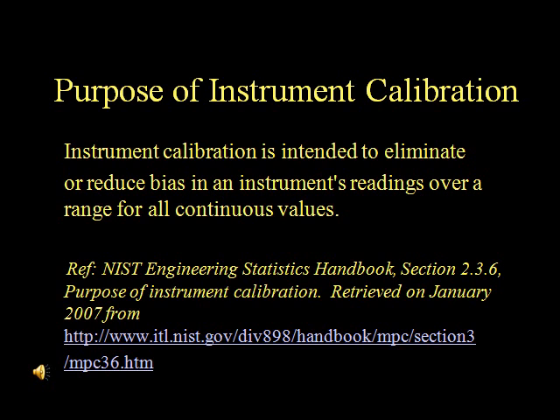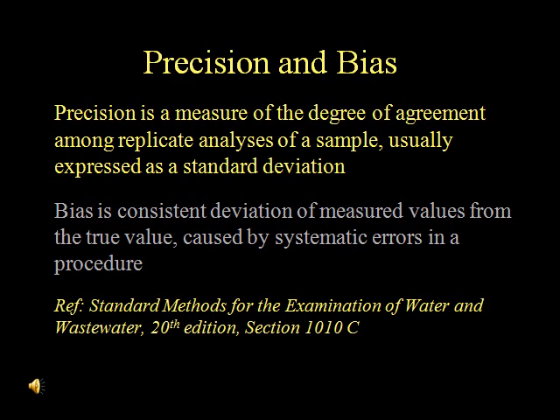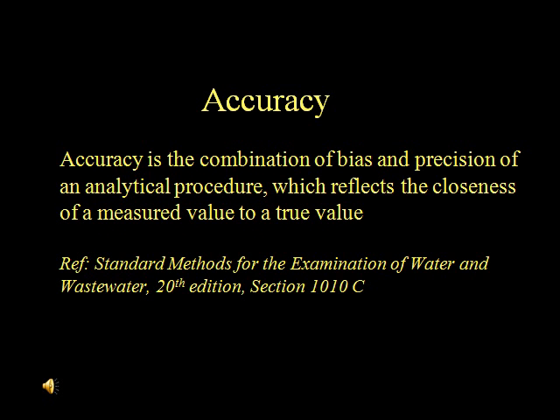The purpose of the instrument calibration, according to the National Institute of Standards and Technology, or NIST, is intended to eliminate or reduce bias in an instrument's readings over a range of all continuous values. Important measurement concepts related to the calibration are precision, bias, and accuracy. Precision is a measure of the degree of agreement among replicate analysis of a sample, usually expressed as a standard deviation. And bias is consistent deviation of measured values from the true value caused by systematic errors in a procedure. Last, accuracy is the combination of bias and precision of an analytical procedure, which reflects the closeness of a measured value to a true value.